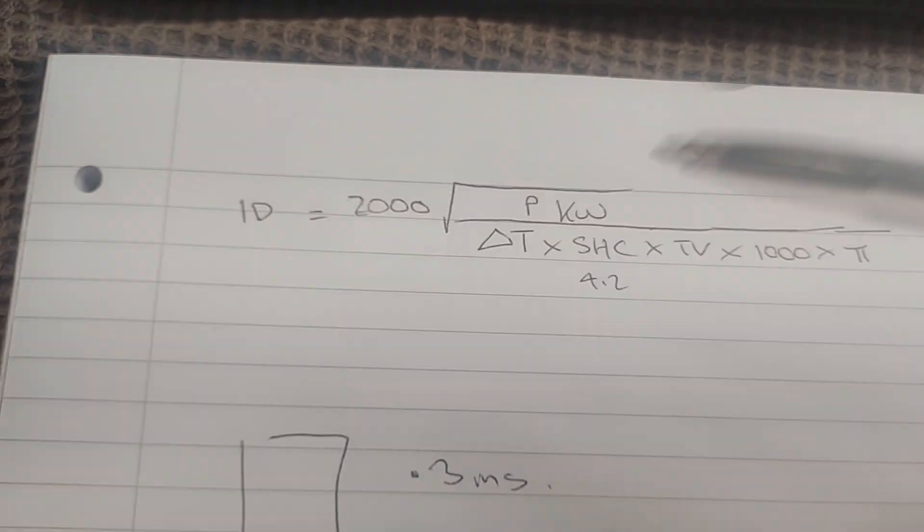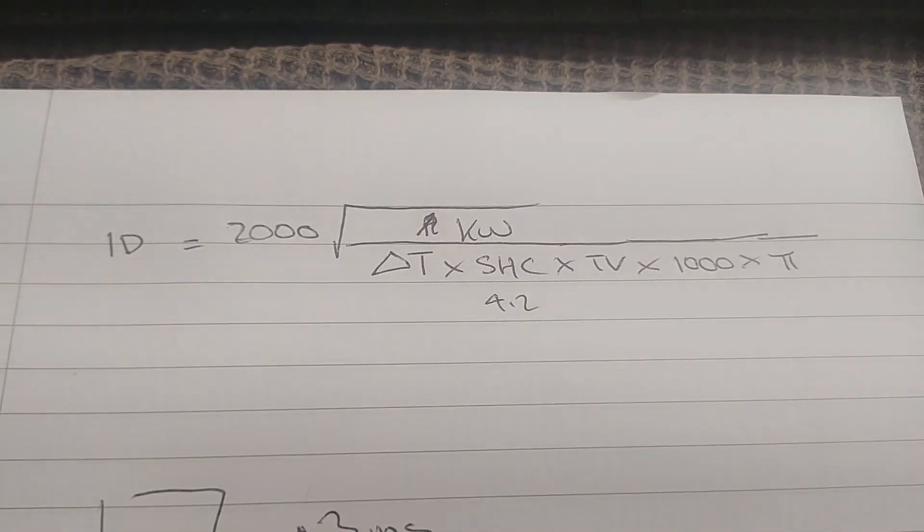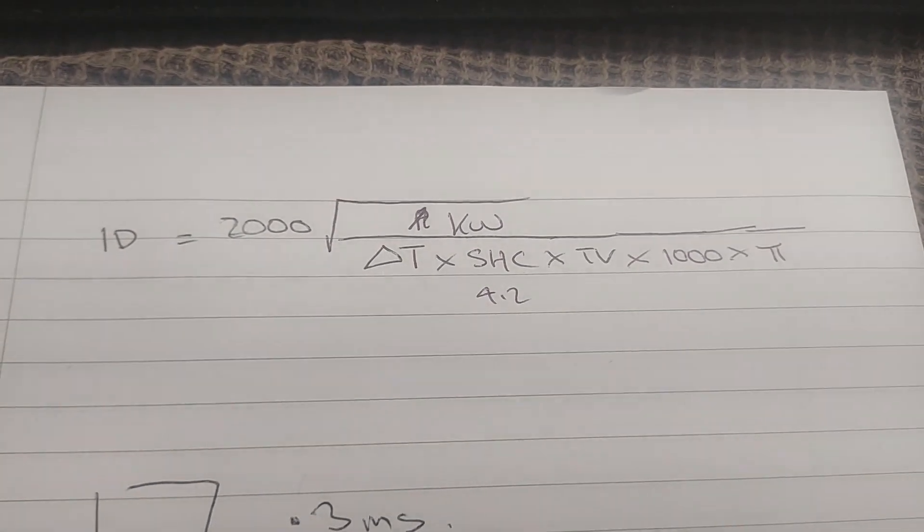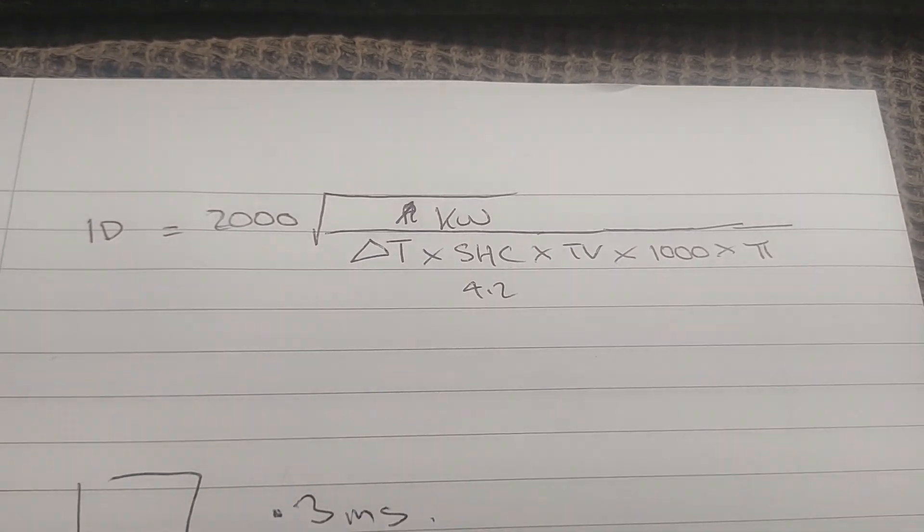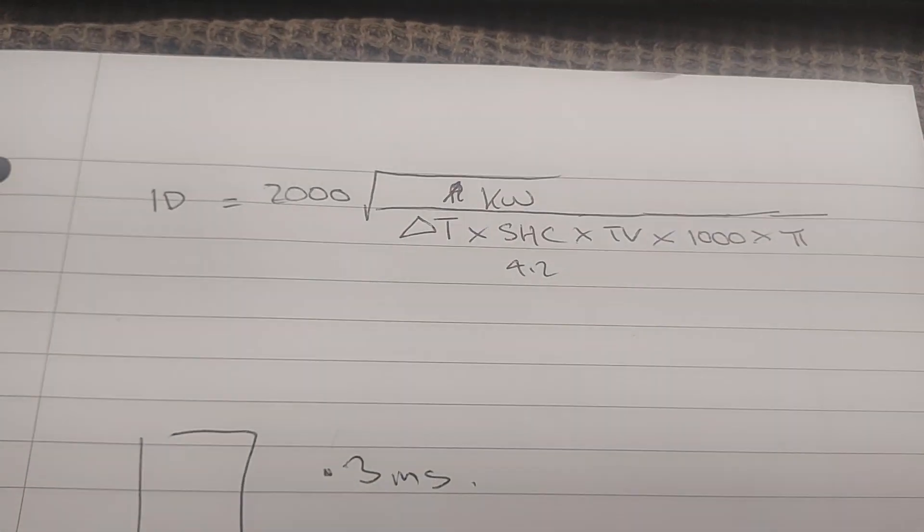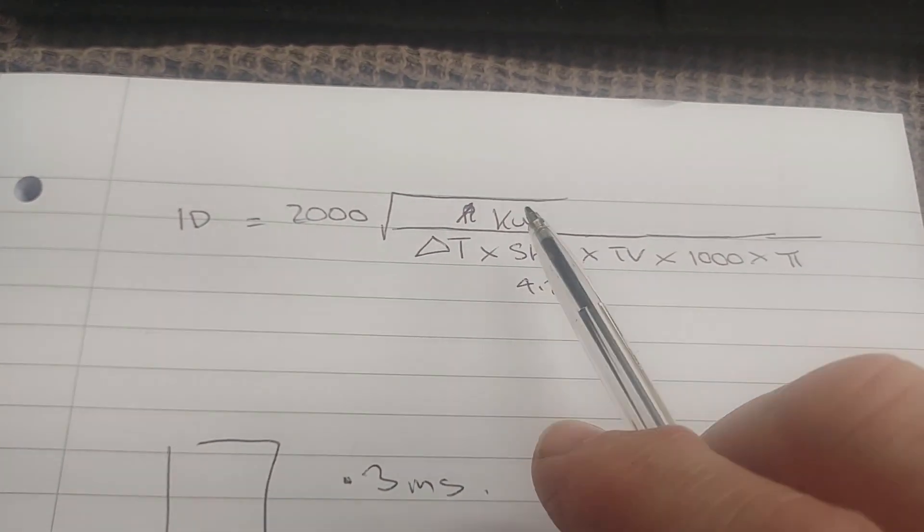If you want to get a chance to take a screenshot there, it's not proper units. So we've got the ID equals 2,000 times the square root of the kilowatt being carried in the circuit or the power carried in the circuit divided by your delta T, specific heat capacity, target velocity, 1000, and pi.